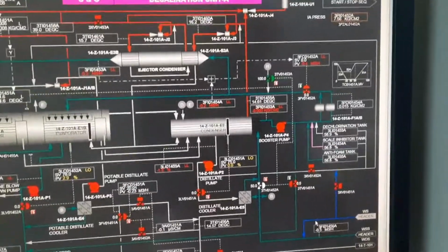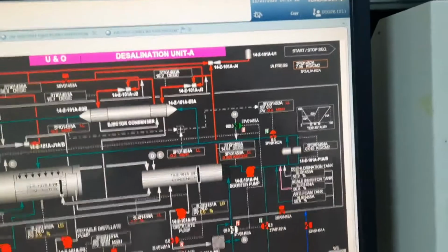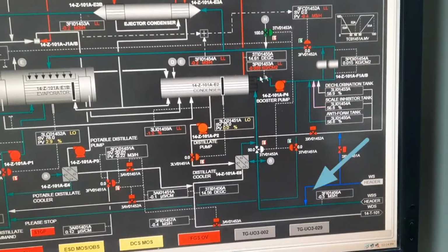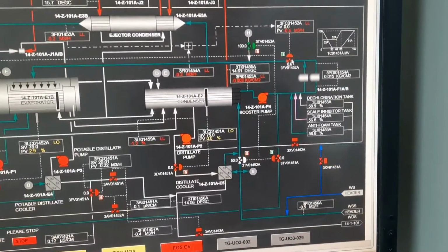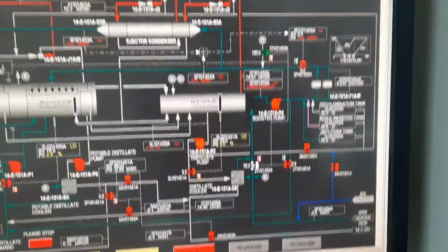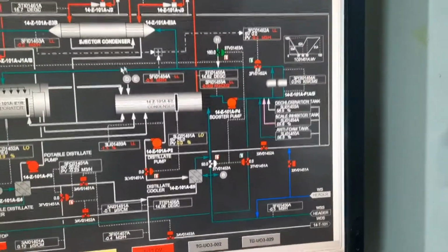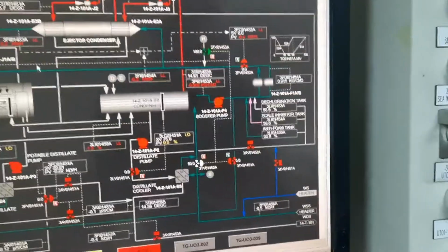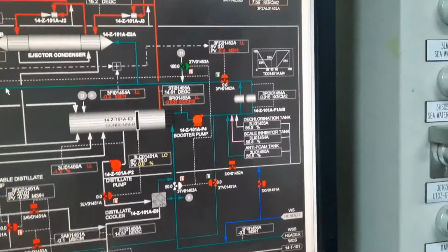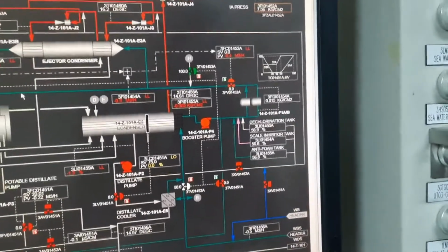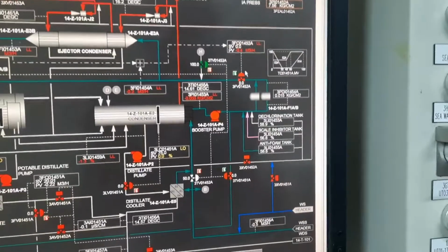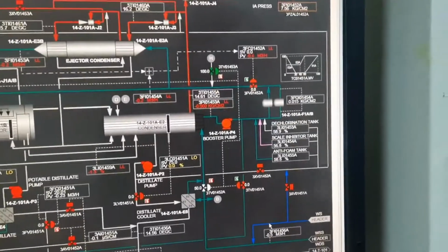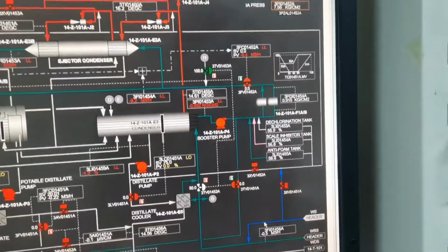After that we will open this local side one water valve, this service water valve. By this line, the water will go to this side. It will pass through the control valve and go to evaporator cell 1 and cell 2. Before doing this operation, we need to check that one valve on the cell 1 side and one valve on the cell 2 side are open. Confirm locally whether they are open or not. After confirming these 2 valves are open, you have to open the spraying control valve and after that open the local side service water inlet valve. Okay.